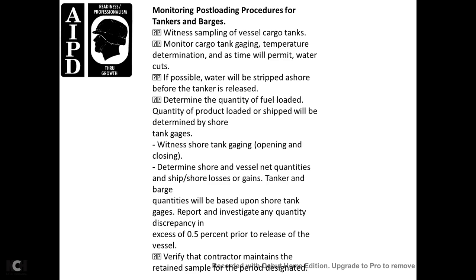Pre/post-loading for tankers and barges: witness sampling of the vessel cargo tanks, including cargo tank gauging, temperature determination, and time permit water cuts. Strip water ashore before releasing the tanker. Determine the quantity of fuel by shore tank gauges. Witness shore tank gauge opening and closing readings. Investigate and report any quantity discrepancy in excess of 0.5 percent prior to releasing the vessel.